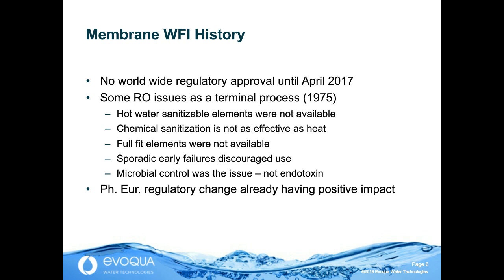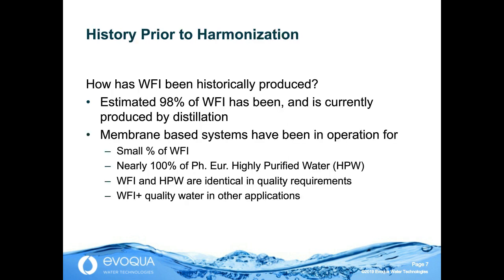In those early systems, endotoxin attainment, conductivity, and in those days it was wet chemistry, but the equivalent of conductivity and total organic carbon, those were not the areas of failure. It was sporadic failures in micro, the 10 colony forming units per 100 mL for water for injection. And even though they were not common, the sporadic failures in some instances discouraged more use. So it was proven that it could work, but the designs were not nearly as consistent as today. How has WFI been historically produced? Well, 100-plus years ago, distillation was the only practical method, and with regulators not allowing other methods in many parts of the world, most WFI is still produced by distillation.